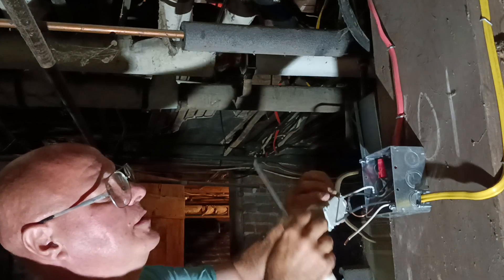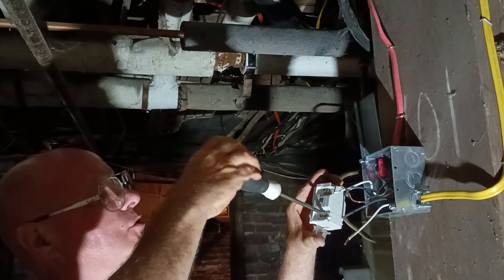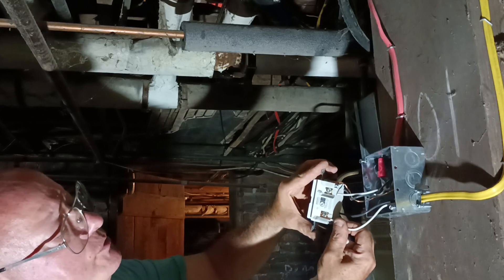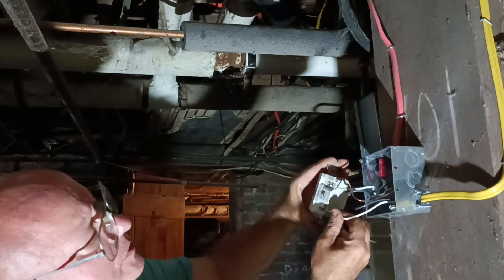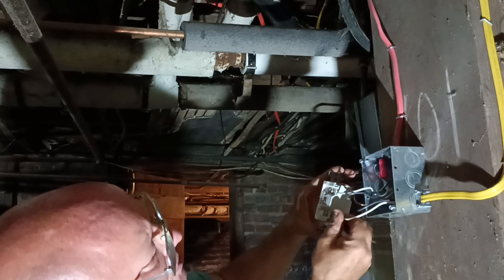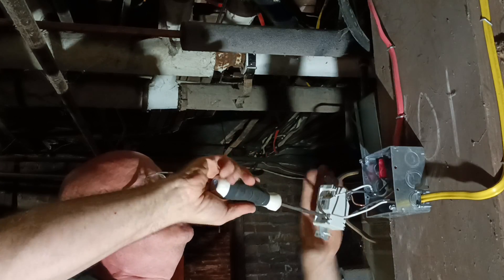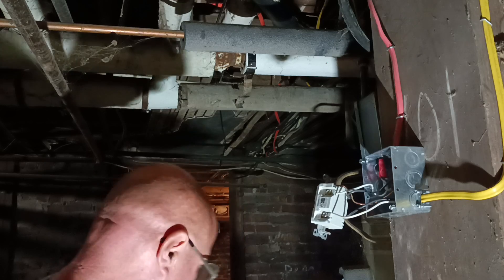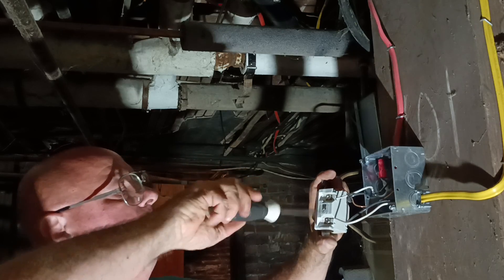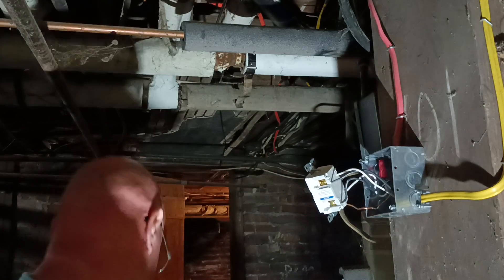We'll come over here and get our white wire screw opened up. Make sure it's long enough — that's a perfect length right there. See how our copper just meets the bottom of our pressure plate. Put it in our load side hole. Make sure it's tight. Use our flat head to torque it down. Now we can fold our wires back into our box here.